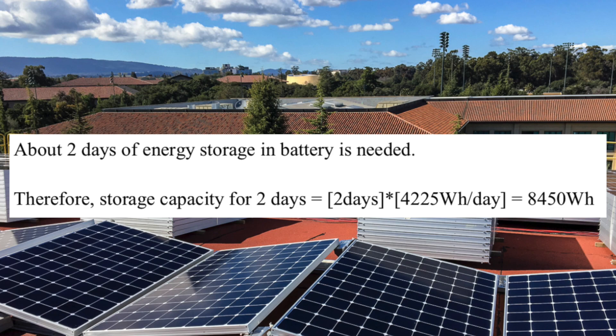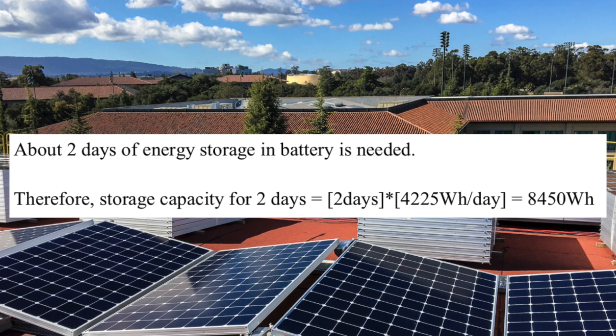In the solar system, we also need to determine the autonomy of the battery. When I say autonomy, I mean how long can a battery last if there was no external power to recharge it — for example, during a hurricane, rainfall, or one to two weeks without sun. We can decide to design a system with a battery autonomy of two days. If we have a load of 4,225 watt-hours per day and we need batteries to give us two days autonomy, the storage capacity of the batteries will be 2 × 4,225 = 8,450 watt-hours.